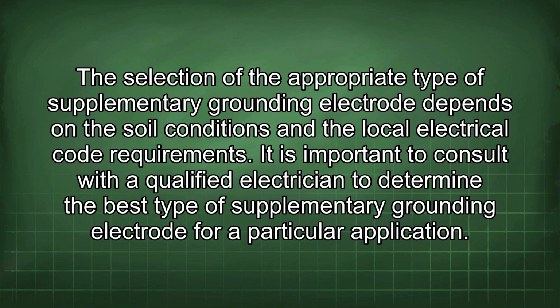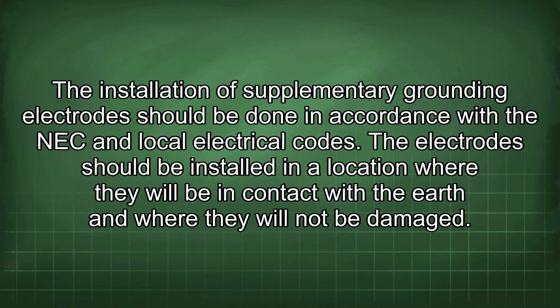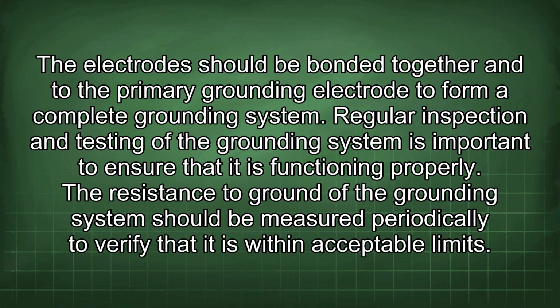It is important to consult with a qualified electrician to determine the best type of supplementary grounding electrode for a particular application. The installation of supplementary grounding electrodes should be done in accordance with the NEC and local electrical codes. The electrodes should be installed in a location where they will be in contact with the earth and where they will not be damaged. The electrodes should be bonded together and to the primary grounding electrode to form a complete grounding system. Regular inspection and testing of the grounding system is important to ensure that it is functioning properly.